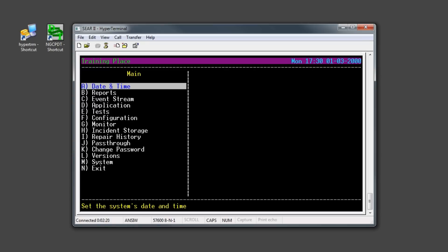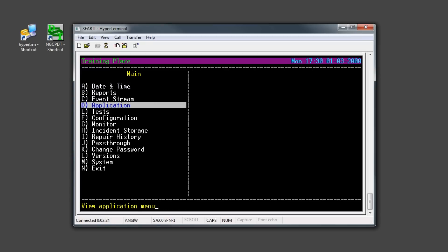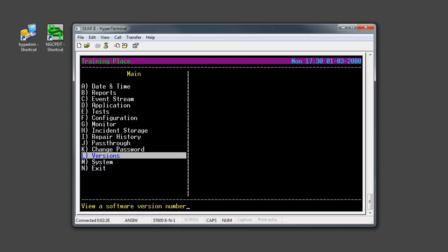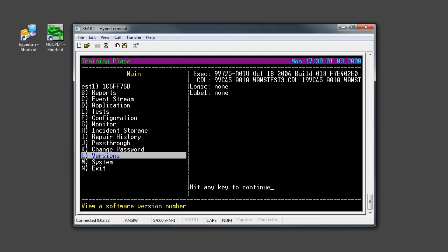The first thing we'll need to check is the versions. You can either hit the letter L or scroll down to Versions and press Enter. The current versions running in the SEER 2i will show up on the right-hand side of the screen. If the executive software needs to be upgraded, you'll need to reboot your SEER 2i unit and follow the prompts at the beginning of the boot process.